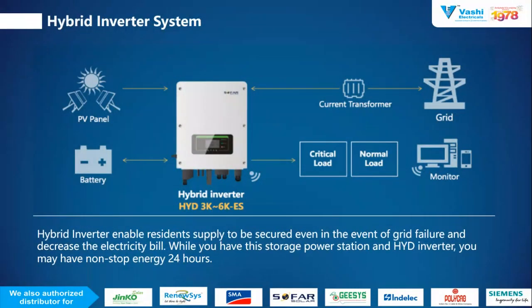So this is the diagram of hybrid inverters. As you can see, there is a PV connection and battery connection at the input side, your left side. There is a PV panel connection and battery connection at the input side, and your normal load and critical load connected with the inverter. At the right hand side, you can also see a connection of a CT with the inverter. This CT provides the fluctuation of load current, meaning whatever load is used by the client is continuously changing. So we have to provide that feedback to the hybrid inverters. According to that, the hybrid inverter will change the generation power and provide it to charge the battery or to export the surplus energy to the grid.